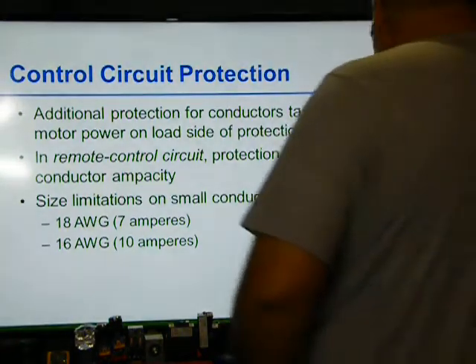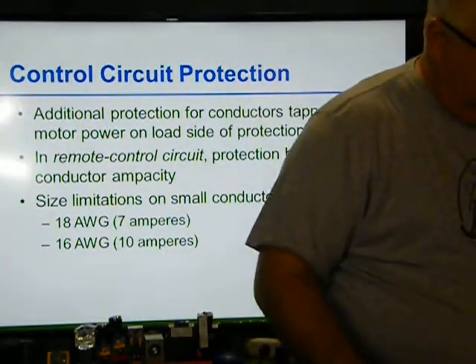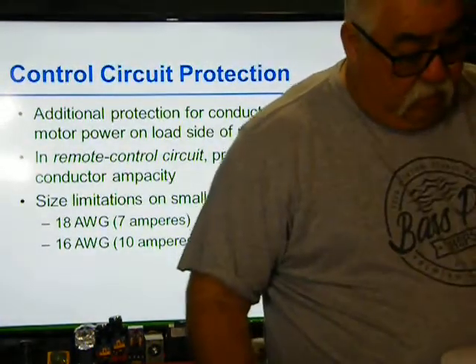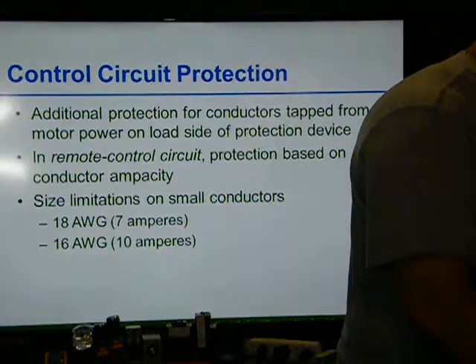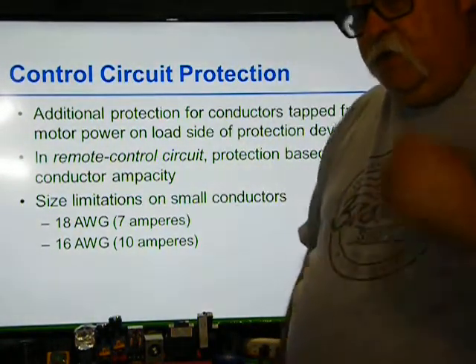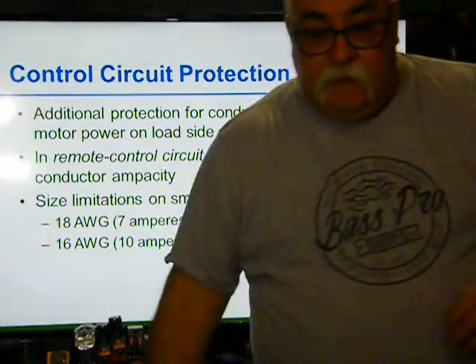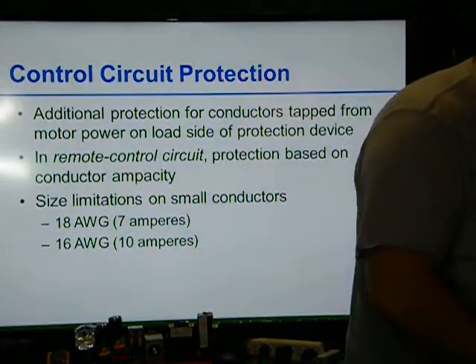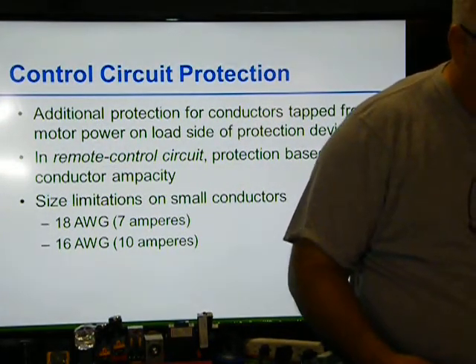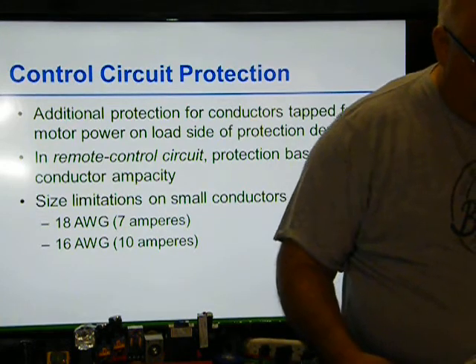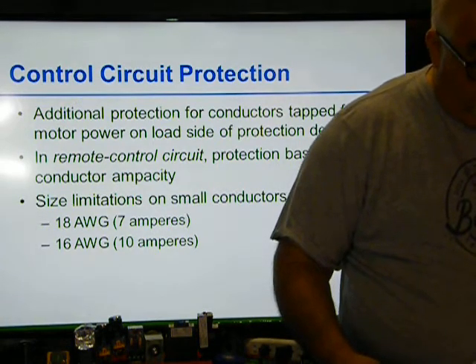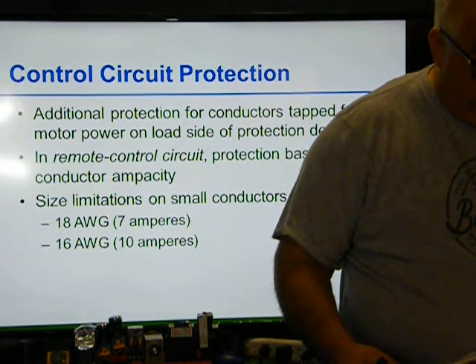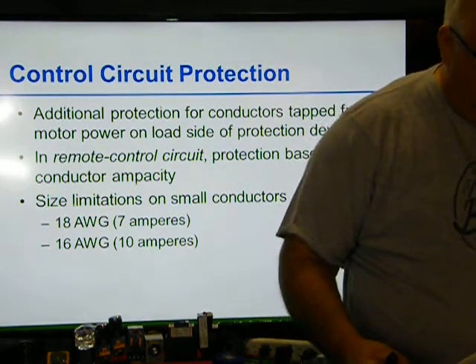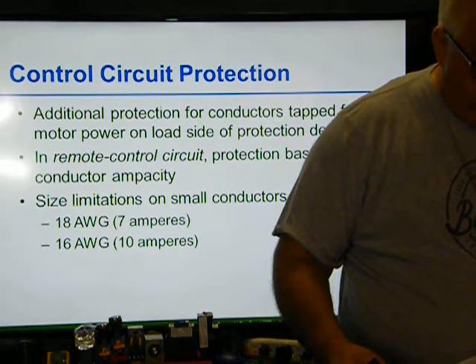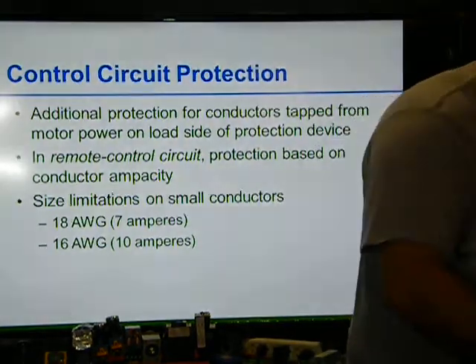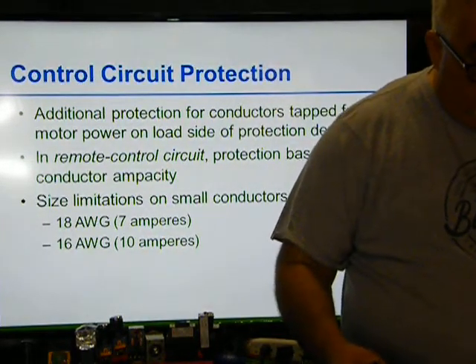It says control circuit conductors must have overcurrent protection. When the control circuit becomes overloaded and opens, the circuit must also open. So in case we overload that circuit protection, it opens up and opens everything else up, since something else may be tied into it. When the conductors are tapped from the motor conductor on the load side of the protective device, the control circuit conductor must have supplemental protection. The maximum rating of the control circuit overcurrent protection device is based on the conductor size. These values are listed in Table 430.72(B) of the code. Control circuit conductors can also be supplied by a separate source, such as service equipment or a power panel.